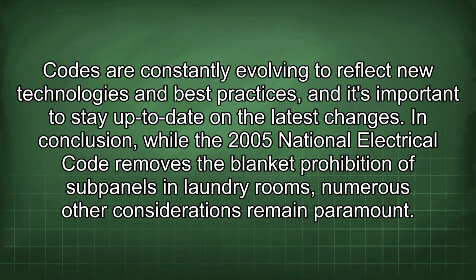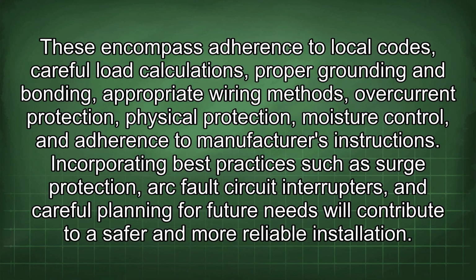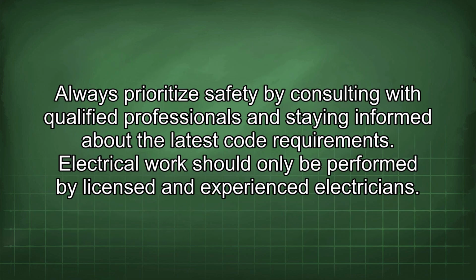on the latest changes. In conclusion, while the 2005 National Electrical Code removes the blanket prohibition of subpanels in laundry rooms, numerous other considerations remain paramount. These encompass adherence to local codes, careful load calculations, proper grounding and bonding, appropriate wiring methods, overcurrent protection, physical protection, moisture control, and adherence to manufacturer's instructions. Incorporating best practices such as surge protection, arc fault circuit interrupters, and careful planning for future needs will contribute to a safer and more reliable installation. Always prioritize safety by consulting with qualified professionals and staying informed about the latest code requirements. Electrical work should only be performed by licensed and experienced electricians.